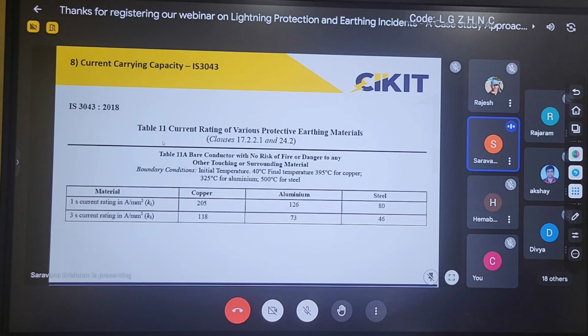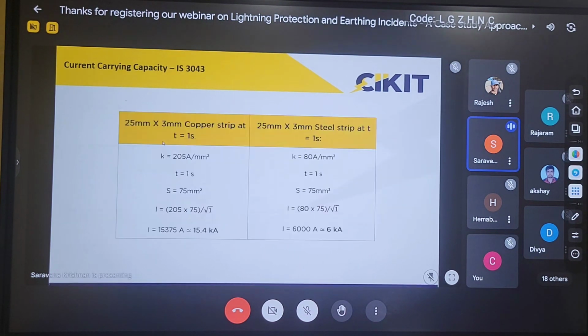So I am just showing the calculation for the copper strip and the steel strip. If I take a 25/3 copper strip, for 1 second, the cross-sectional area is the same and the duration is also the same, whereas the value of K will be different for copper and steel. So if I am going for copper, the value will be 205, whereas for steel it will be only 80. So that will be around 2.6 to 2.7 times difference. If I perform this calculation, I can find that a 25/3 copper strip will have a current carrying capacity of 15 kA for 1 second, whereas for a steel strip of the same dimensions, it will be only 6 kA for 1 second.